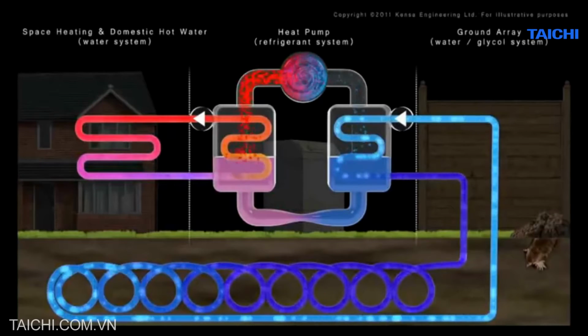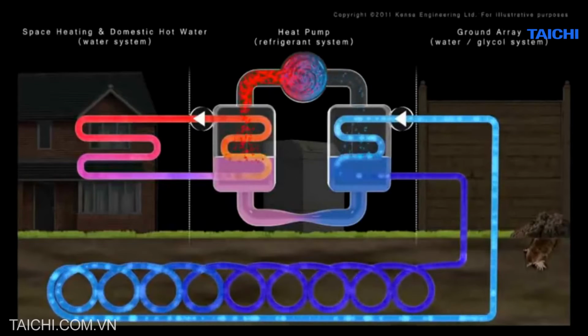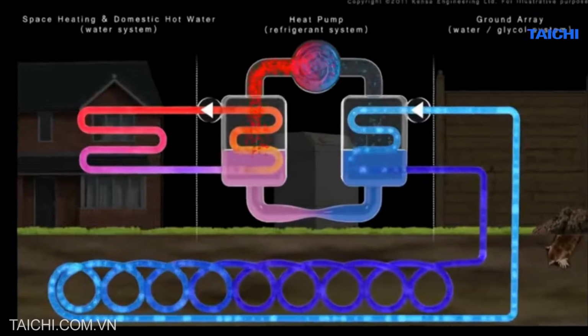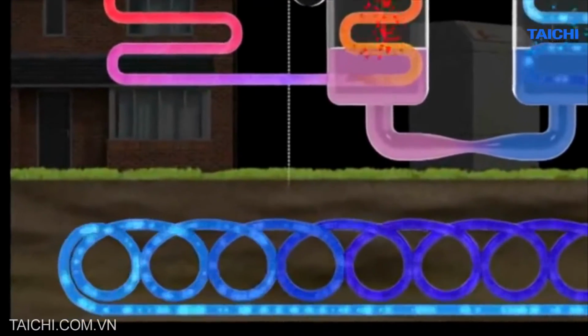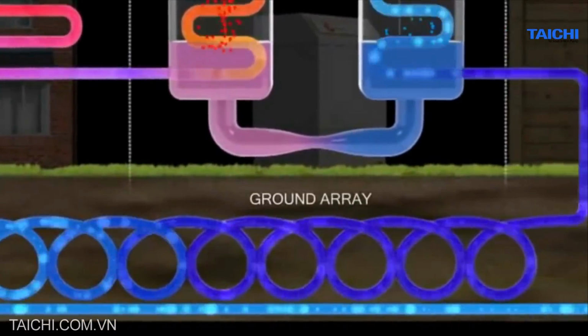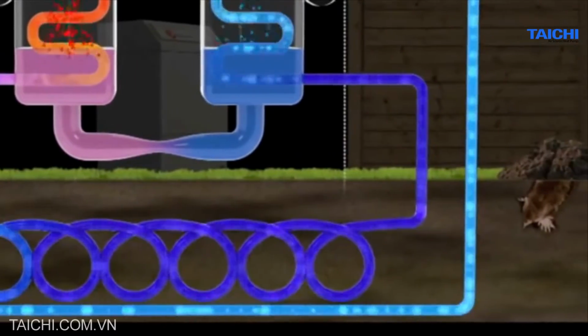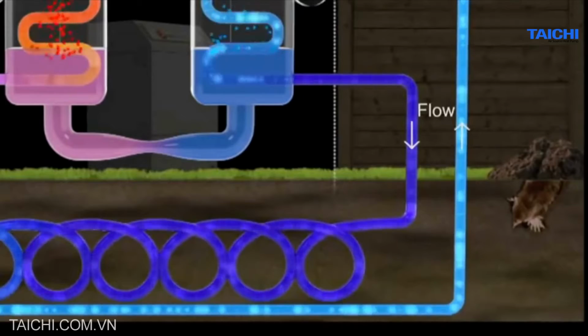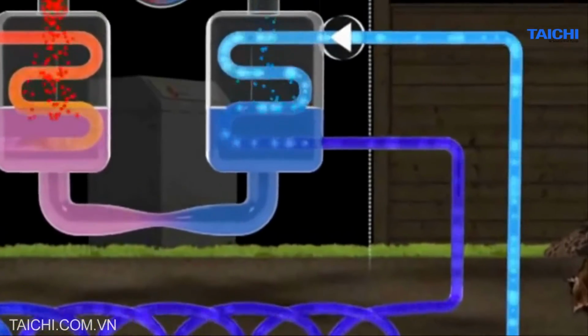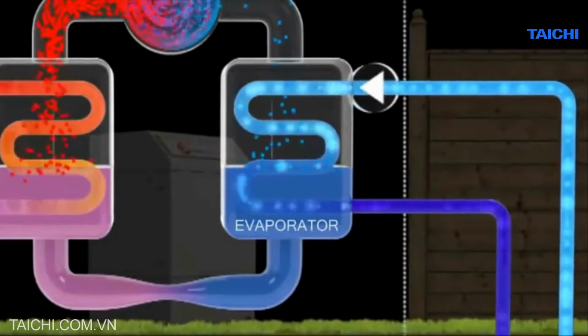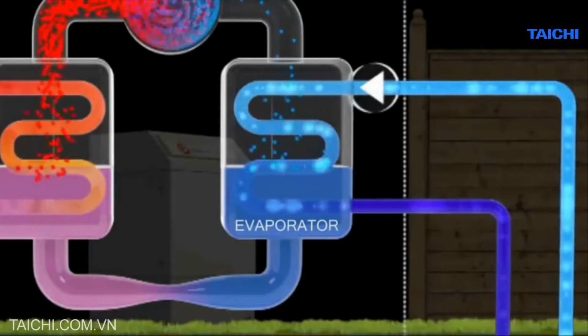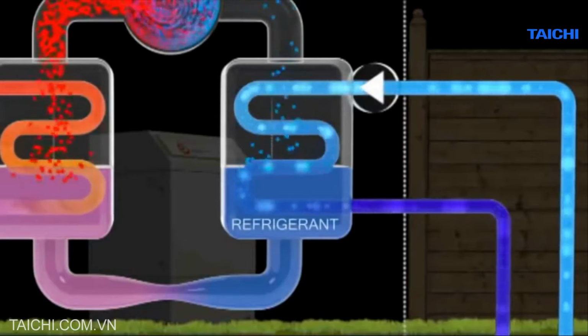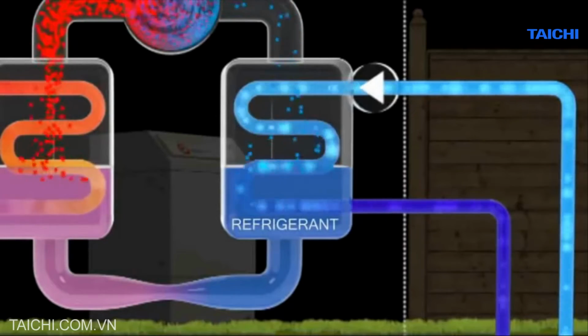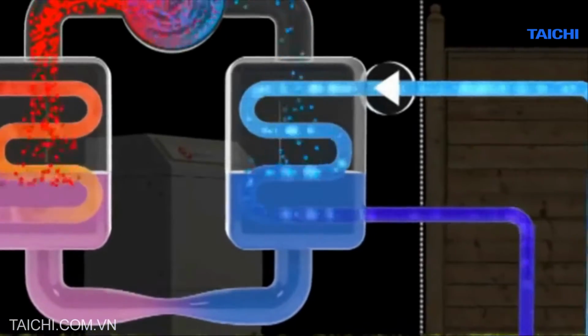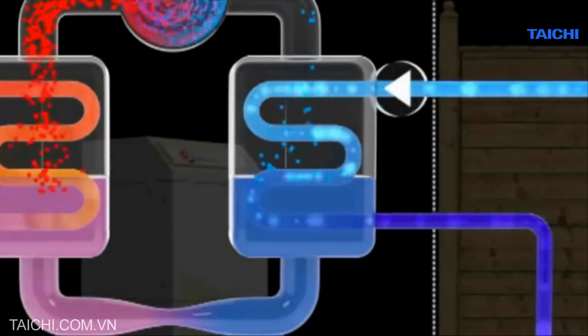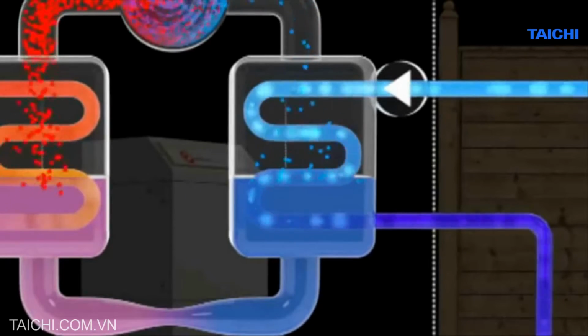A cold water antifreeze mix is pumped through the ground within a series of energy-absorbing pipes known as ground arrays. As heat naturally flows from warmer to cooler places, the antifreeze mix circulating around the array is constantly warmed by the ground's low-grade heat. Having increased in temperature, the antifreeze mixture is fed into a heat exchanger called the evaporator. Within the secondary sealed side of the evaporator heat exchanger is a refrigerant which acts as a heat transfer fluid. When the water antifreeze mixture enters the evaporator, the energy absorbed from the ground is transferred into the refrigerant, which begins to boil and turn into a gas.